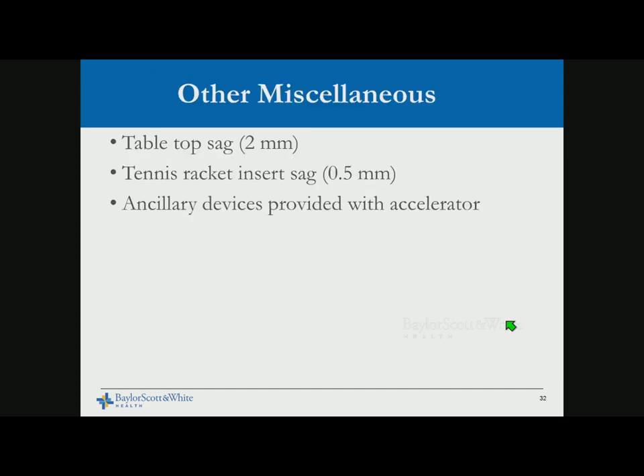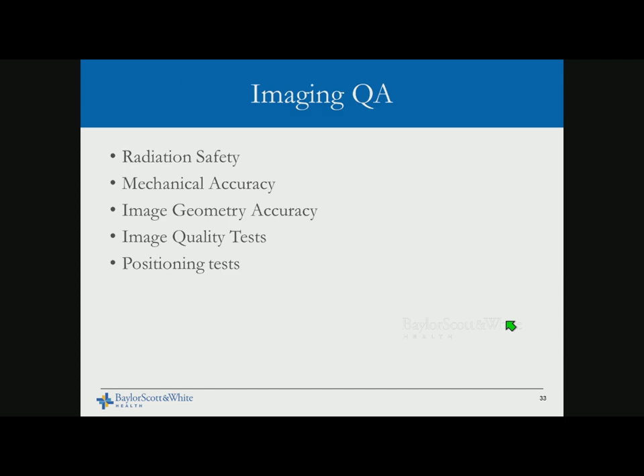Other issues include table sag, table transmission, and additional devices like RPM respiratory gating systems. We have many task group reports piecemealing each component, but at acceptance testing it is challenging to hold the vendor accountable for these. When you have additional devices like RPM, knowing which recommendations to follow is unclear.